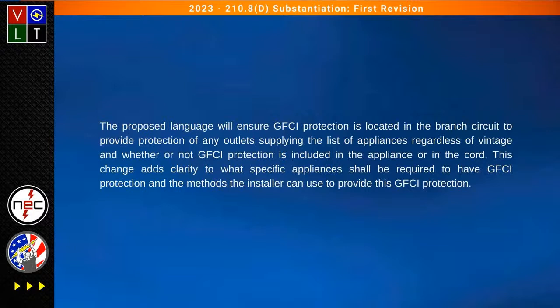And this is an interesting thing where they say, even if GFCI protection is included in the appliance or the cord. So what they're saying is, even with a drinking fountain - I was really ridiculed on this - even if you have a GFCI protected water cooler, let's say, and it has its own integrated cord with GFCI protection in it, they still want the inspector to say you need a GFCI protected receptacle that it plugs into. And they even say they don't care if it has two devices on it, they're okay with that. So this is an interesting twist. I was kind of destroyed on this a little bit, on the water cooler one.